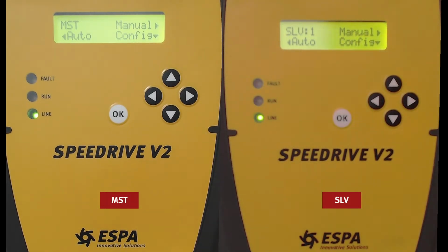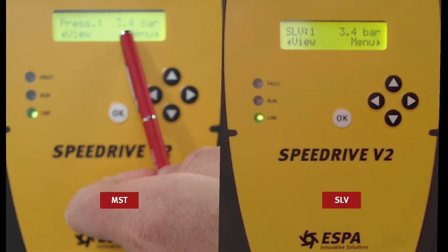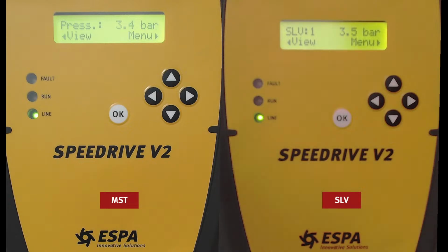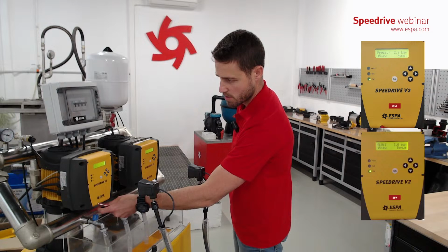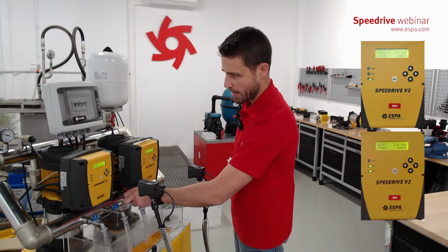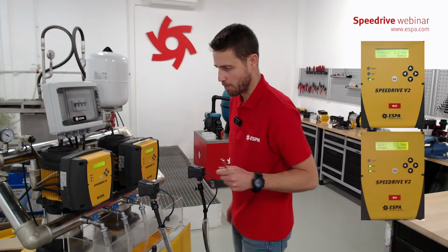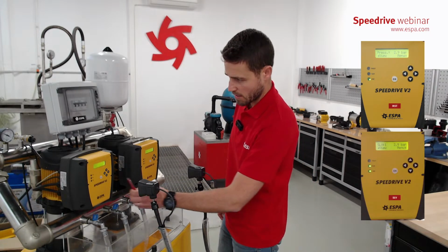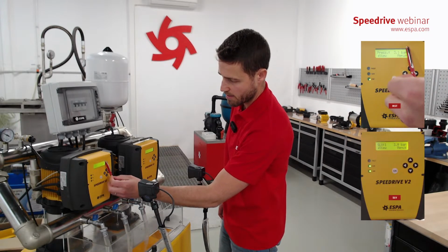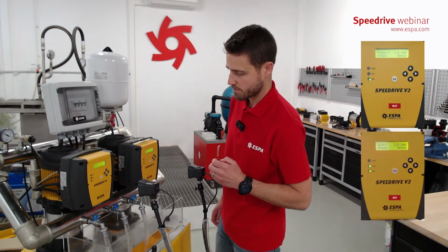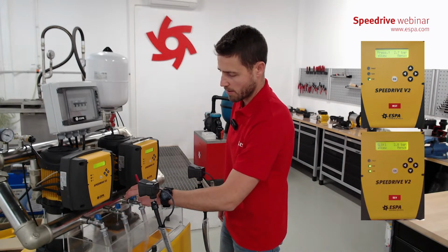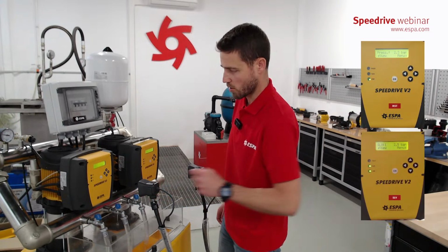Now, in order to check if it's working at the pressure that we have set, we can go to auto mode. The pressure that we read via transducer shows us 3.4 bar, but we have set it at 3. So we have to open the valves and create a flow, the pressure will go down, and right now the pumps have started. You can see the pressure is maintained at 3 bar. The more I open the valves, the faster the pumps will go.